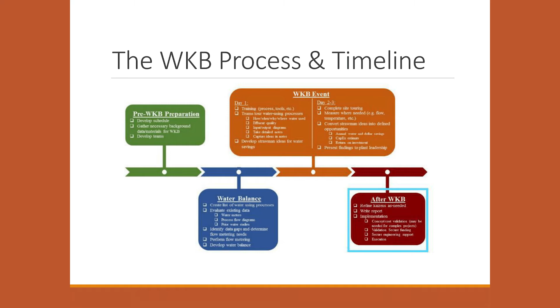Common places that we want to look are, we want to compare the actual flow to the required flow. We want to compare delta T anywhere where water is being used for heat exchange. We want to make sure that water is only flowing when it's needed. Sometimes in manufacturing processes, water is going to a system 24/7, but people are only using it 16 hours of the day. So we want to identify situations like that where we can easily reduce some of this waste.